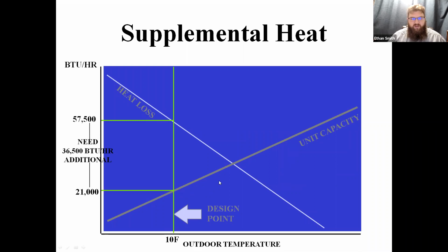Or what we can do is do a supplemental heat balance point instead of replacing 100% of the unit at 10 degrees. So we know that below whatever this temperature is, we'll call it 37, we need to add heat. But maybe we keep the heat pump running instead of shutting it off completely. And so what we would do then is we know that at 10 degrees outdoor temperature, by our performance charts that we looked at before, we know that this heat pump will generate 21,000 BTUs of electric heat.